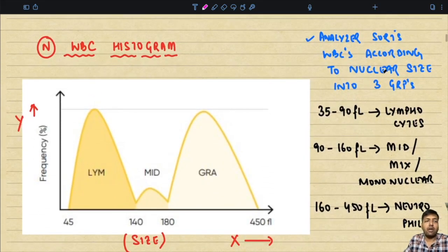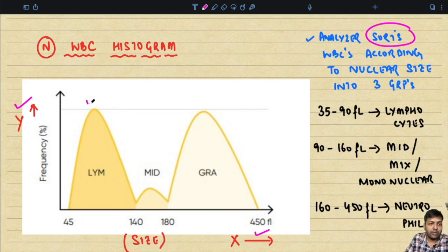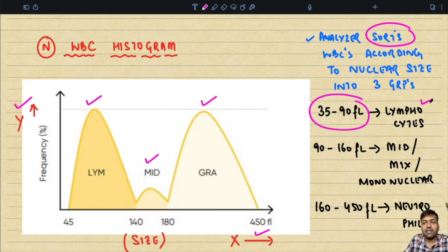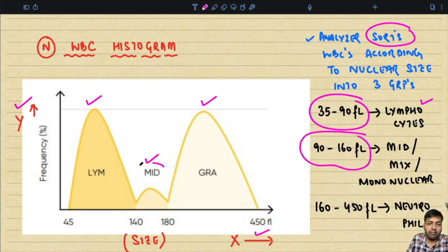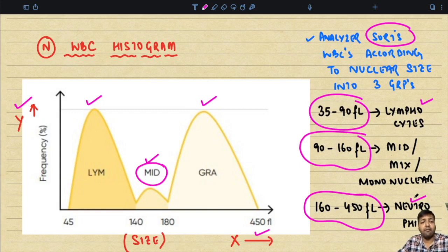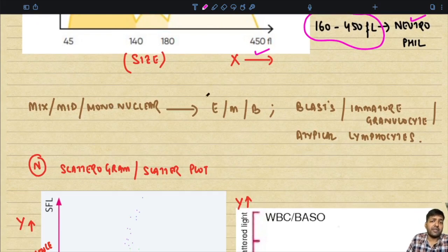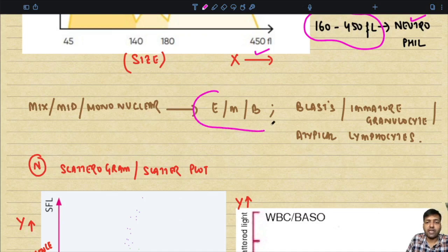Now let us understand what a WBC histogram looks like. In the normal WBC histogram, size is plotted on the x-axis and frequency or count is on the y-axis. The analyzer sorts WBCs according to nuclear size into three groups: lymphocytes (35–90 femtolitre), the middle or mix group (90–160 femtolitre), and granulocytes (160–450 femtolitre). This is how the machine differentiates between these three populations of cells.